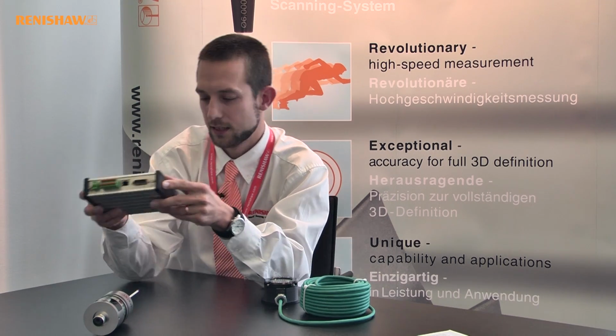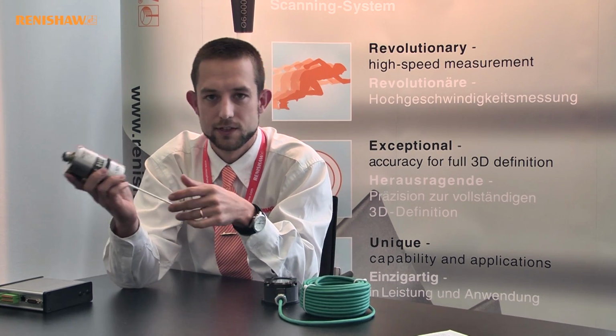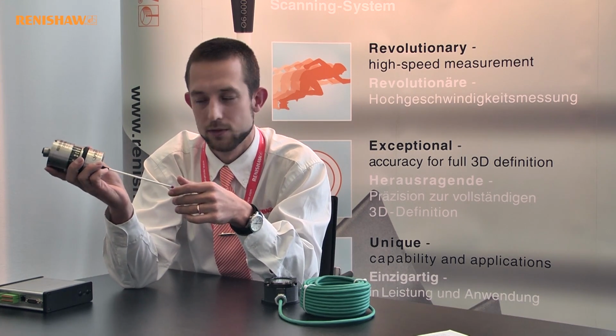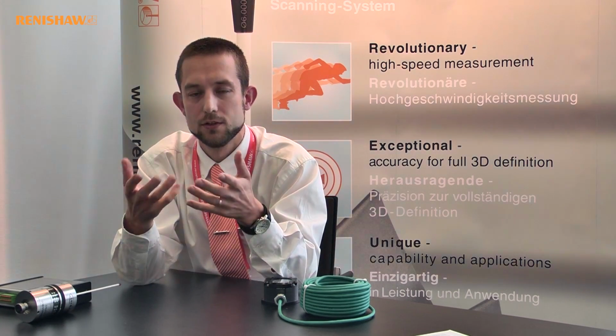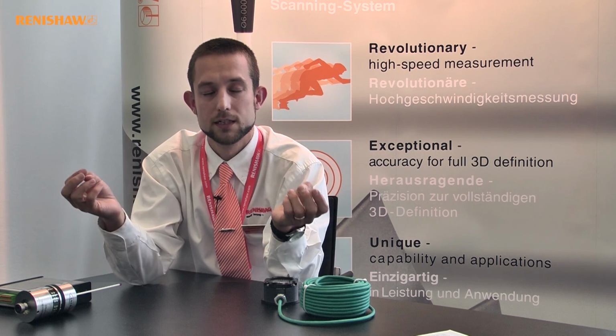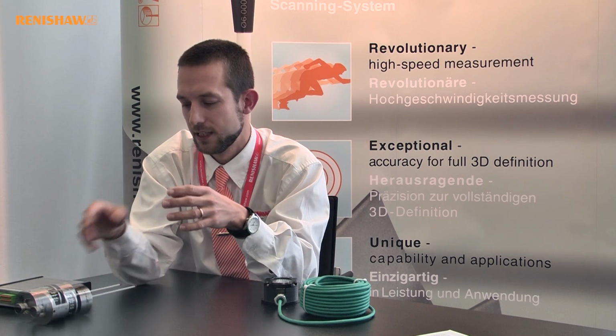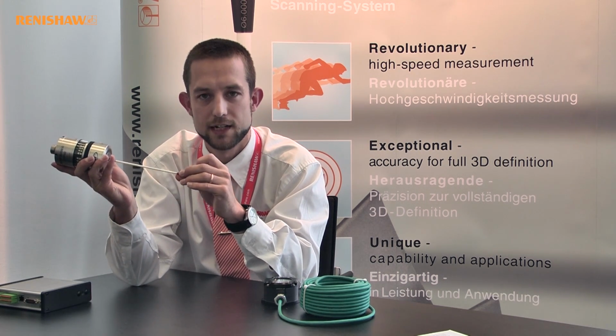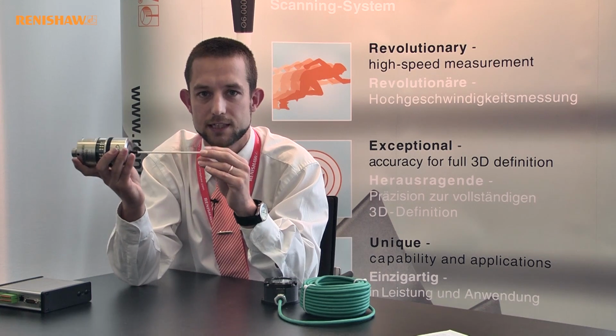So connected into this, there is a piece of software called the Productivity Plus CNC plugin, and what the CNC plugin does is it takes the 2 streams of data. One of them is the 3-dimensional probe deflection data from the Sprint OSP60, and the other one is the stream of position data coming from the encoders or coming from the CNC machine tool controller. In the CNC plugin software, we can combine those 2 streams of data, and using various calibration or compensation techniques which are calculated during the initial setup of the probe, we get a very accurate reading for the position of the stylus tip.